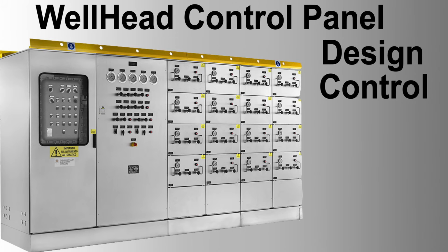Operation: 1. Normal operation. The WHCP maintains hydraulic pressure to keep the ESD valve open. 2. Emergency shutdown. In case of critical alarms or manual activation, the PLC RTU vents the hydraulic pressure, causing the ESD valve to close. Control loop. Closed loop. The pressure transducer provides feedback to the PLC RTU, which adjusts the hydraulic pressure to maintain the ESD valve in the desired state. Feedback: real-time pressure data from the transducer. Control signal: hydraulic pressure regulated by the PLC RTU.